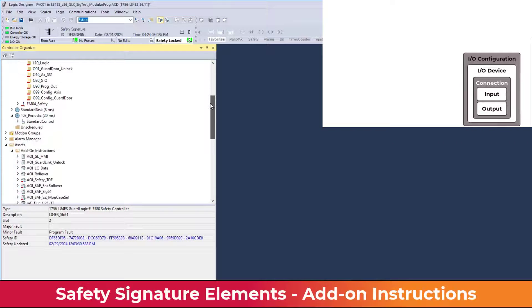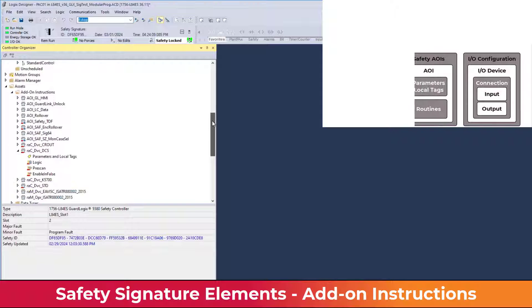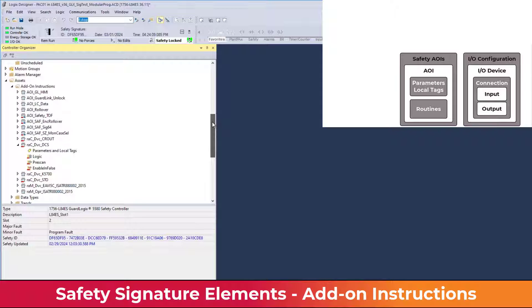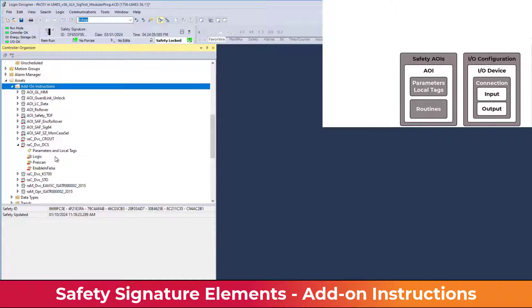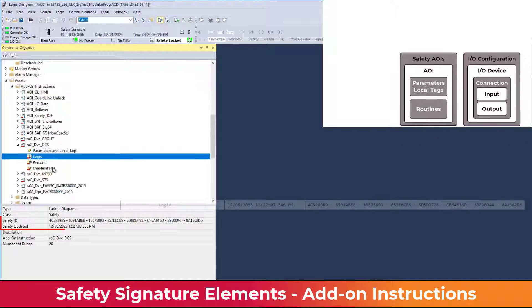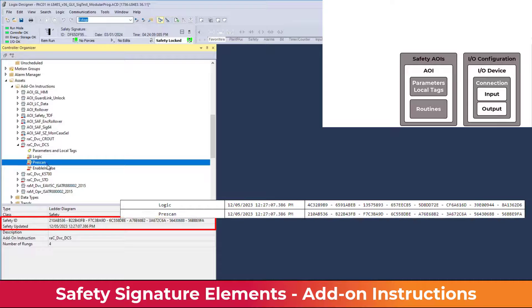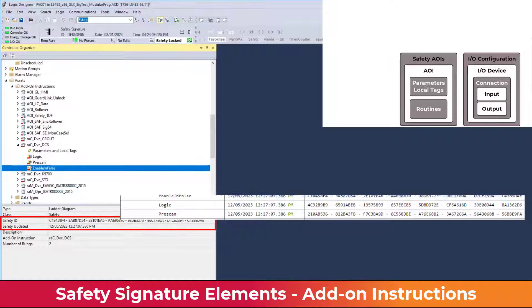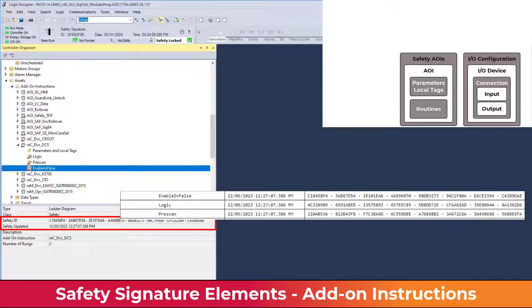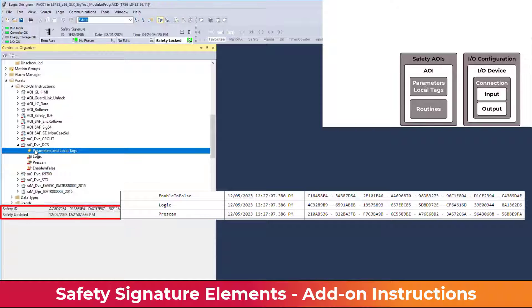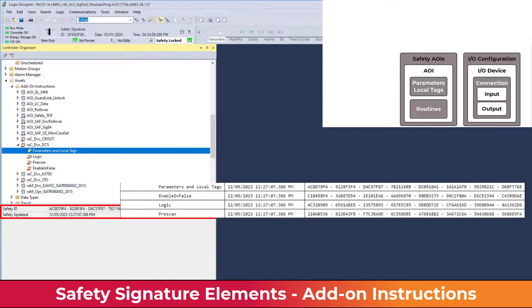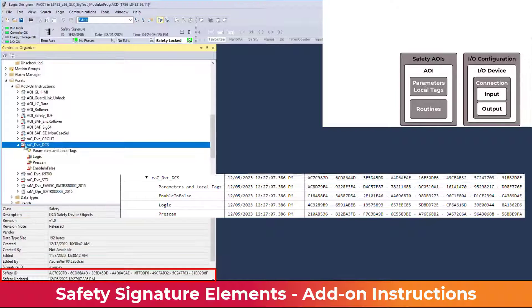Safety add-on instructions have a signature for each routine that is in use. These routines could include the logic, pre-scan, post-scan, and enable-in-false routines. Each add-on instruction's parameters and local tags have a signature, and the overall add-on instruction has a safety signature.